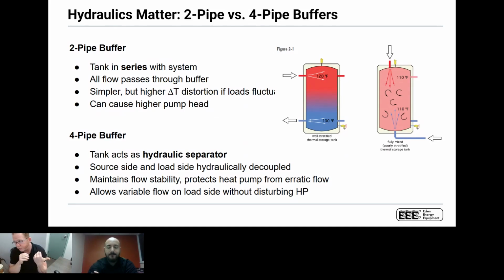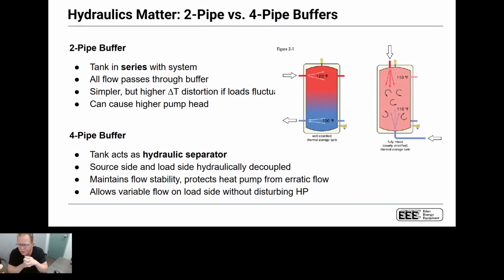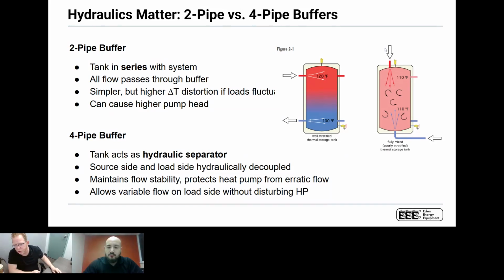From a piping standpoint, we have a few configurations on piping of buffer tanks. You have a 2-pipe buffer tank and you have a 4-pipe buffer tank. So we want to be very conscious of what these systems are. I don't really have any preference on a buffer tank without knowing exactly what the system is. The only thing that I would say to you, and you guys will get the Caleffi manual for this, which is a really good manual to read, that's where this photo is from, is just make sure that you're not dumping hot water into the top of the tank. That is a really good way to make sure your tank is not stratified.